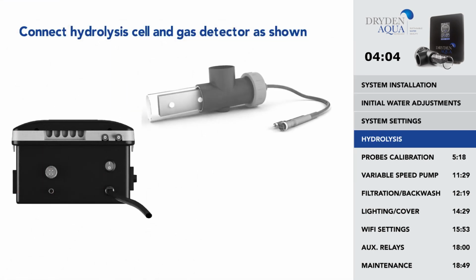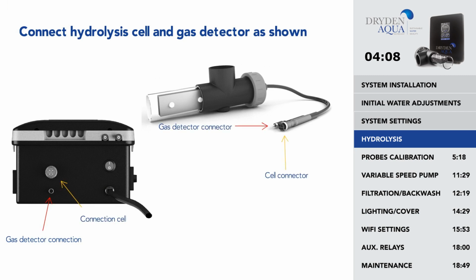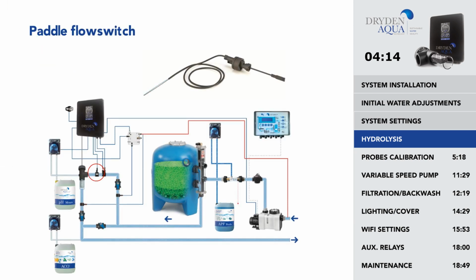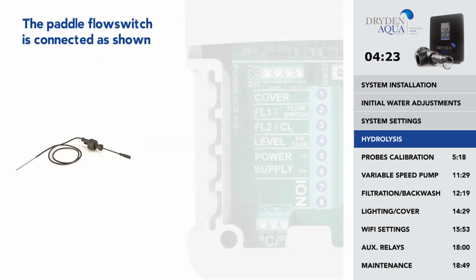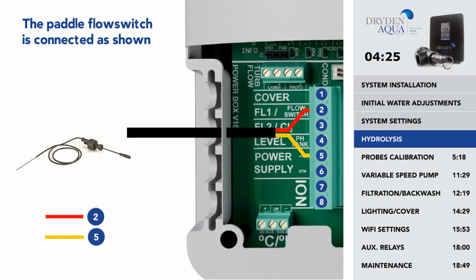Hydrolysis. First, install the hydrolysis cell and connect it to the DA-Gen control box. The hydrolysis cell and its gas detector are connected as shown. Then connect the paddle flow switch. Installed before the hydrolysis cell, the flow switch stops the hydrolysis and the dosing pumps if there is no water flow. Connect it as shown and contact your provider for activation.